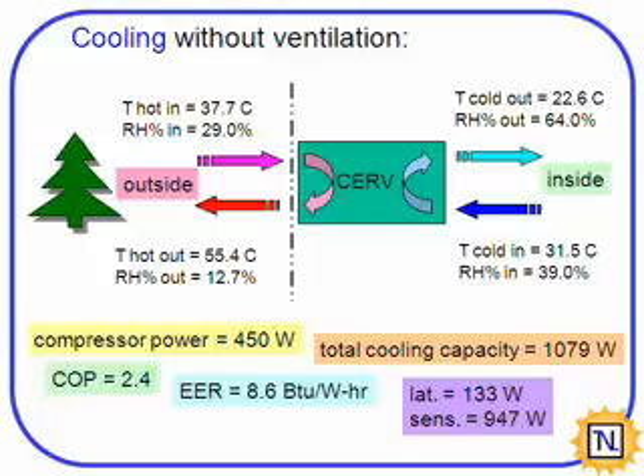These conditions are just ones we've run in our lab, so we've had to do different things, such as taking the outlet air and aiming it towards the inlet to try to trick it into thinking it's a summer day. So the conditions aren't necessarily what you would actually see, but we're just trying to get an idea of the capacity that we're seeing with it. And then here's that latent and sensible loading that was talked about earlier. So about 130 watts of latent, dropping moisture out, and then 940 watts of cooling that air down.